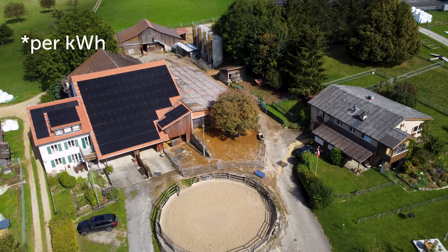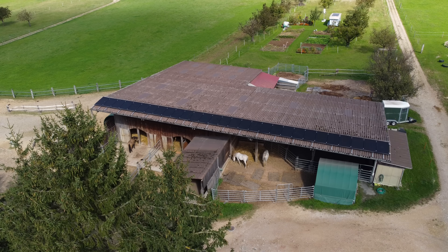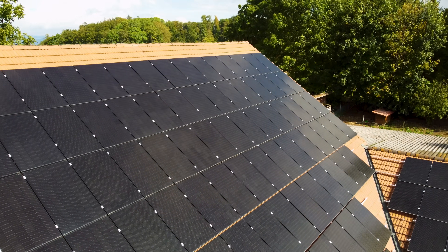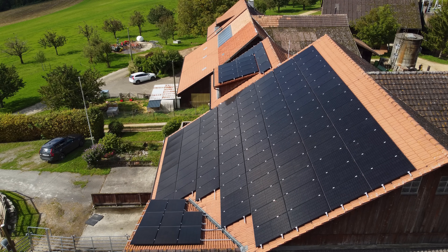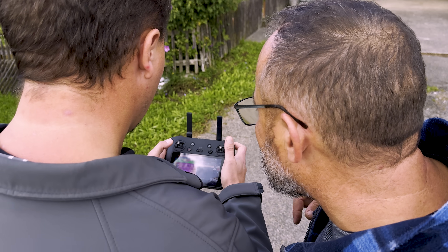Here in Switzerland we earn nearly 15 cents per kilowatt-hour. With this goal in mind they've installed 29 solar panels on the stable roof capable of producing 10.73 kilowatt-peak, plus 125 panels on the main building producing 46.7 kilowatt-peak. The roof was heat-scanned to check for any hot spots or faulty panels. You need a lot of panels, but your target is not to feed the grid as much as possible — it's nice if you have surplus to send back, but on a rainy day you need enough panels to fill your battery for the night.